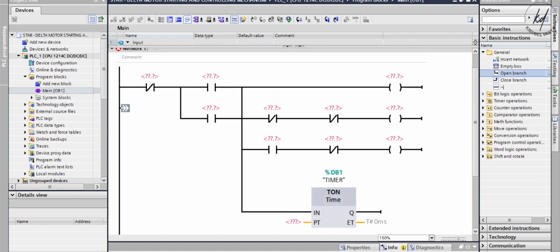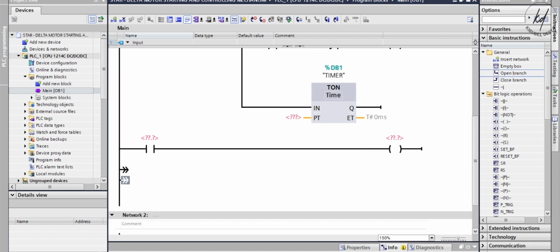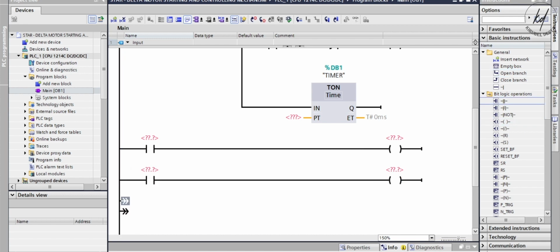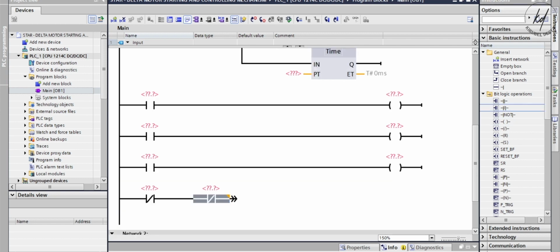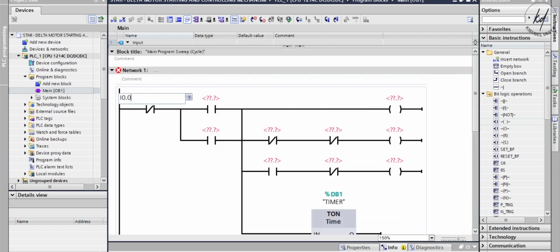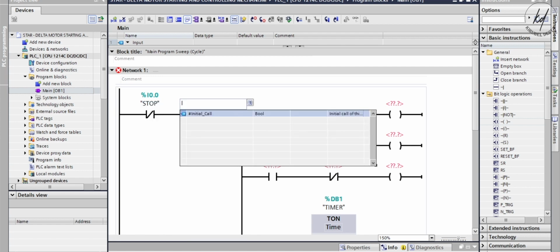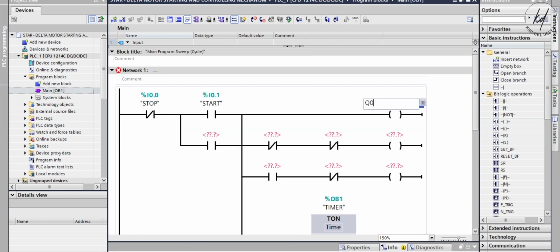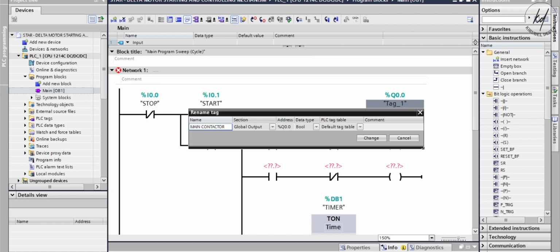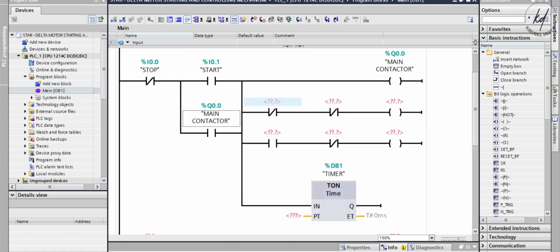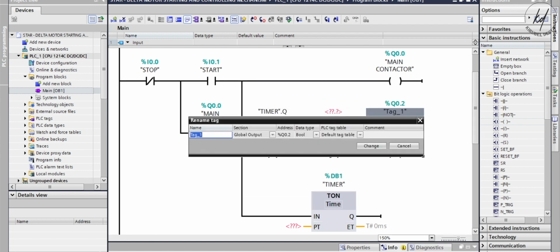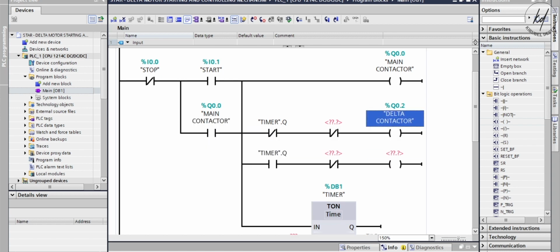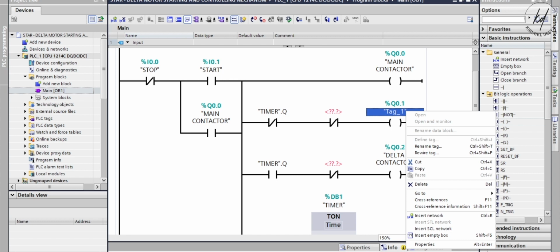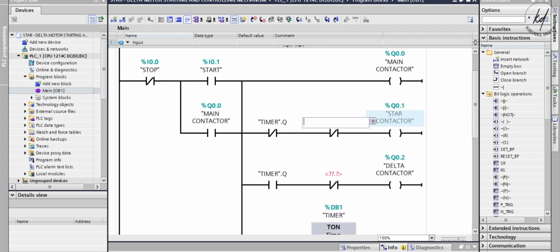Most induction motors start with the DOL (direct online) starter, but when a very large capacity induction motor is started with a DOL starter, it may cause a disturbance on the supply lines due to large starting current surges. To limit the starting current, large induction motors are started at a reduced voltage. The star-delta starter is the popular method to start a large induction motor at a reduced voltage.